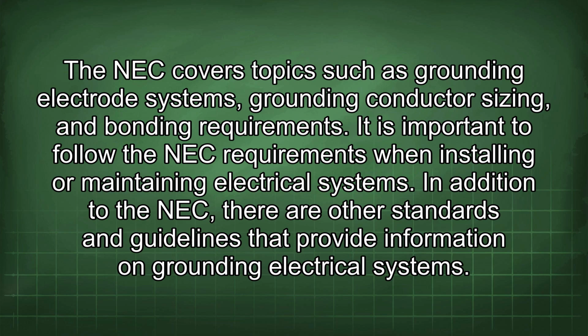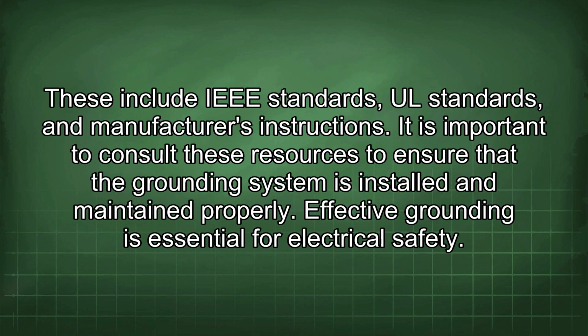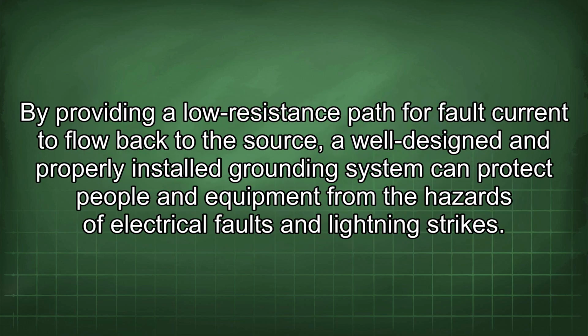In addition to the NEC, there are other standards and guidelines that provide information on grounding electrical systems. These include IEEE standards, UL standards, and manufacturer's instructions. It is important to consult these resources to ensure that the grounding system is installed and maintained properly. Effective grounding is essential for electrical safety. By providing a low resistance path for fault current to flow back to the source, a well-designed and properly installed grounding system can protect people and equipment from the hazards of electrical faults and lightning strikes.